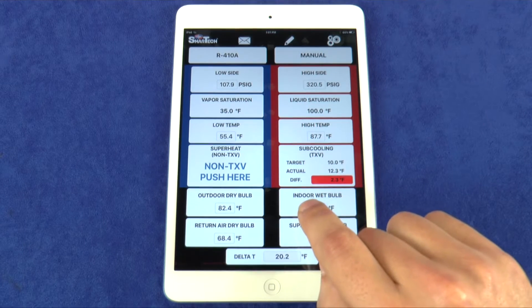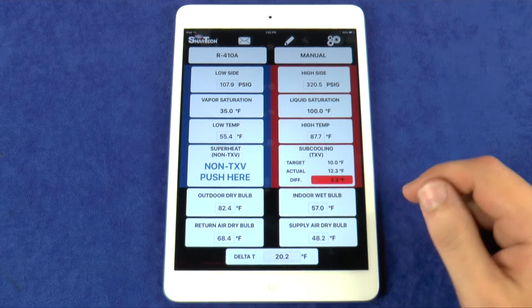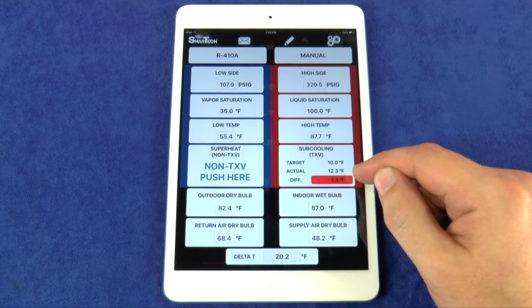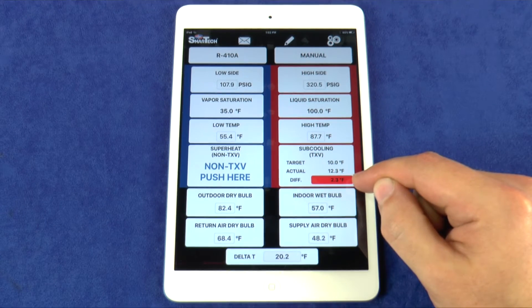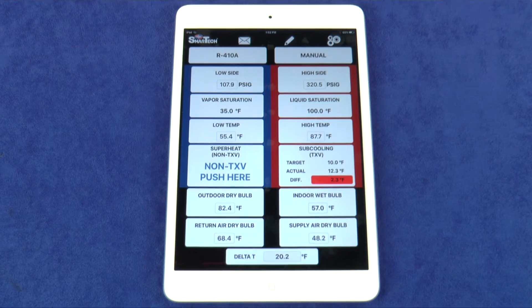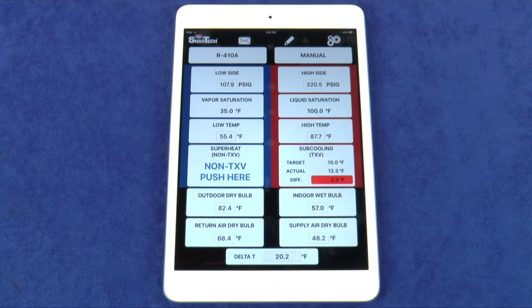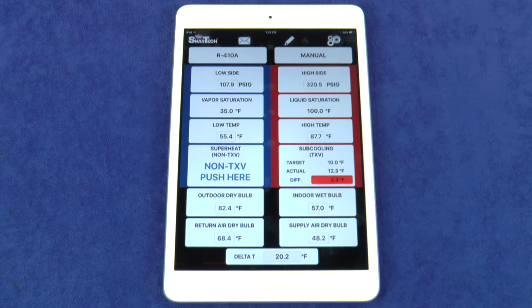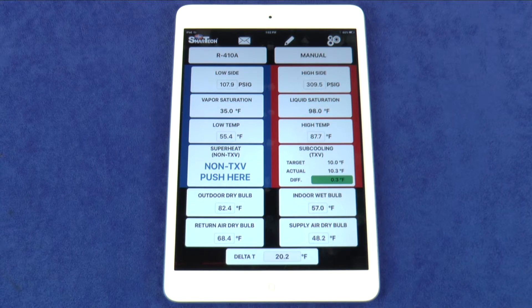This field features the Smart Charge Zone. The difference between the target and actual superheat or subcooling is shown here with color indicators. For example, I've set the subcooling target at 10 and as I change the value for the high side pressure, you will see the color indicator change. Red means the system is overcharged, blue means it is undercharged, and green means the system is properly charged. This makes it very easy to get the perfect system charge for maximum efficiency and optimal performance.